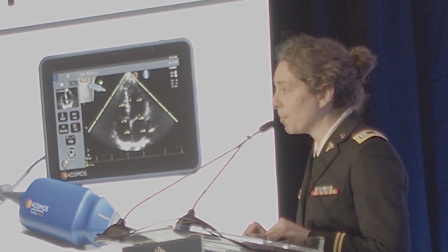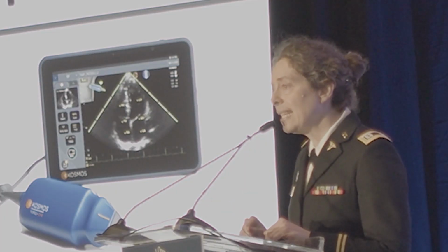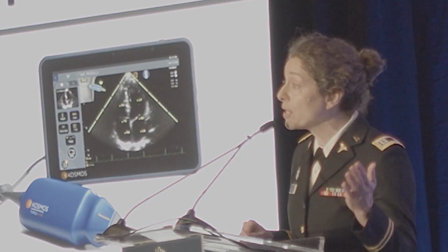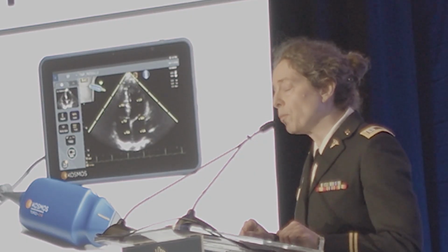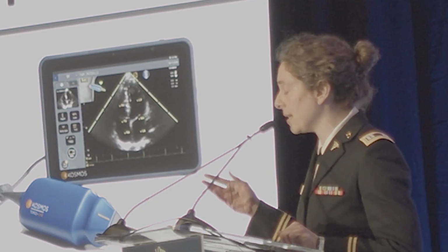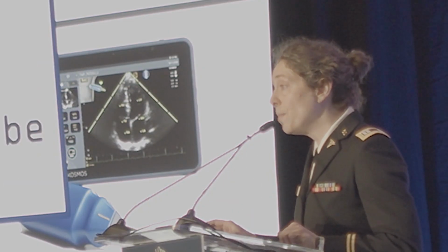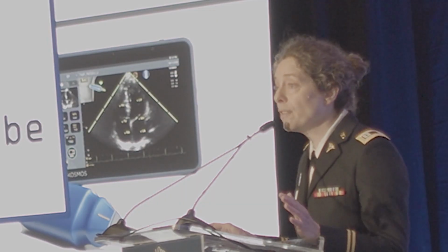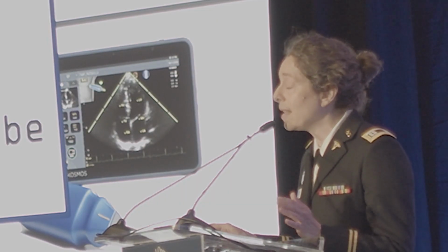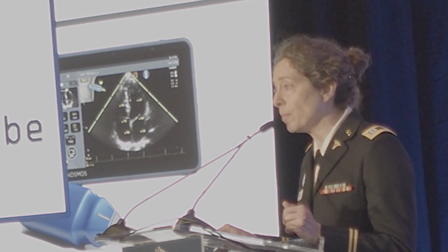We had intended to develop models of the electromagnetic signatures like those that you saw for the 50-watt radio and for the Wi-Fi and Bluetooth-enabled medical devices. But the electromagnetic signature of all of the ultrasound probes was so insignificant that modeling could not be performed.